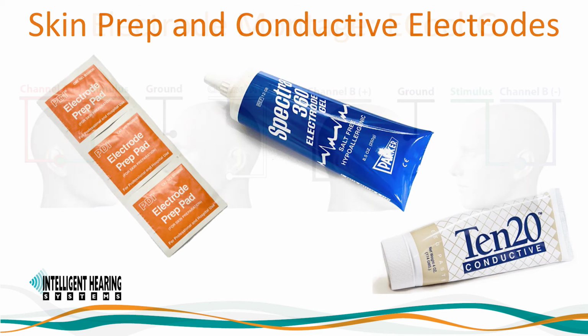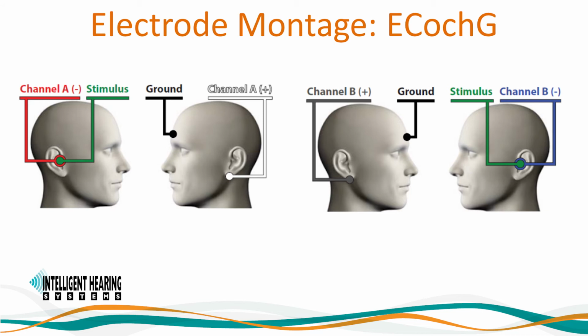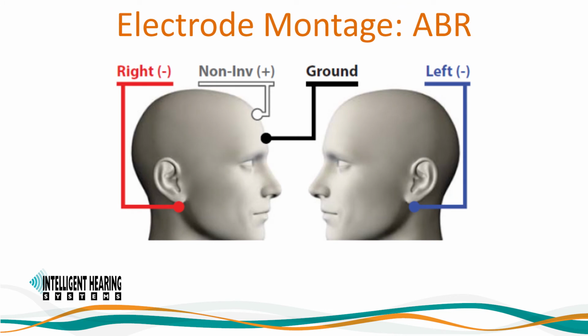Ensure that you are using the correct electrode montage, especially at a site where different machines may be used. Different machines have different naming conventions for their connections, thus verify the electrode montage connections to the device. A typical ABR electrode montage is high forehead as your positive electrode and the negative electrode just behind the ear and level with or slightly lower than the ear canal auditory meatus, allowing for bone conduction placement above. It is a common mistake to place the positive electrode too low and the negative mastoid electrode too high.